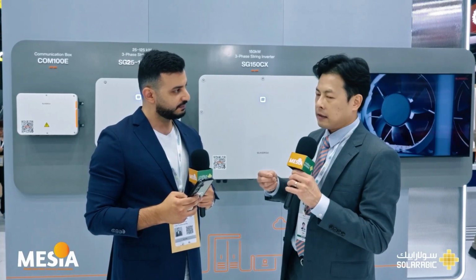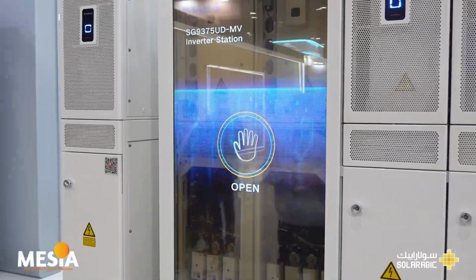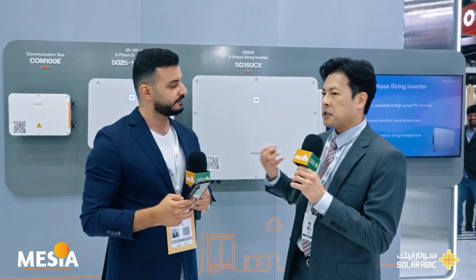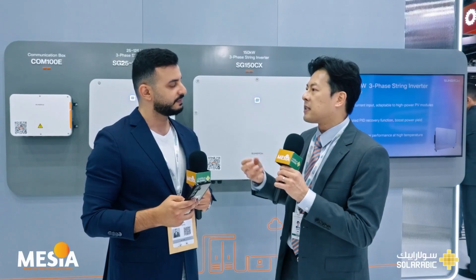Historically, in the past, black start was only about energizing the DC bus bar or the DC systems, right? But at Sungrow, we have moved from simply establishing a voltage to a fully true grid forming capability and technology. This is a new kind of technology that we adopt. It uses virtual synchronous generator functions, which mimic the actual synchronous machine behavior, but in the static way, in the power electronic way. So what it does is provide a very fast response to any disturbance in the system.